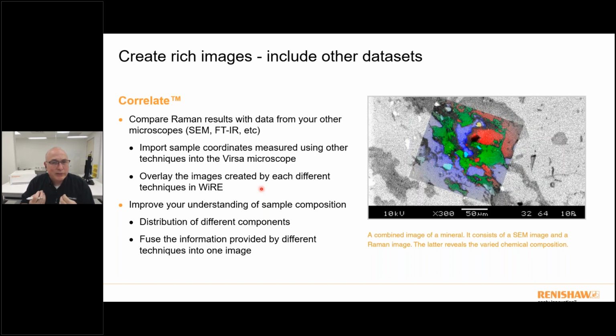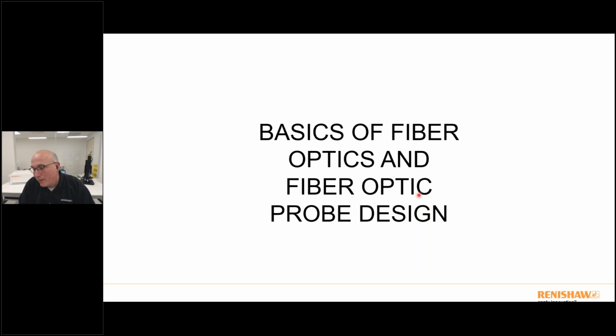So it used to be that I was always saying, if you can see the sample, I can focus a laser beam on top of it and I can get a Raman spectrum of it. But now you don't even need to see the sample with an optical technique. You can use different techniques like an AFM or electron microscope, and you can use those images to define areas where you want to collect Raman spectroscopy. So this is a really interesting functionality that's available freely within the latest version of our WiRE software. Sorry, not all versions, the latest version. That allows us to take those third-party images and bring them into our instrument and use that.